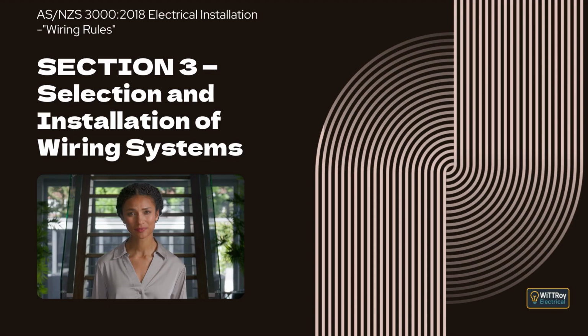Clause 3.12.6 Poles and posts, including supports, struts and extensions to structures. This clause explains that poles and posts used to support aerial conductors must be made from materials suitable for the conditions of use. Their size and depth in the ground must be adequate to provide stability. Where ground conditions are poor, the depth must be increased or other stabilizing methods used. This ensures the support remains secure under load and environmental conditions.